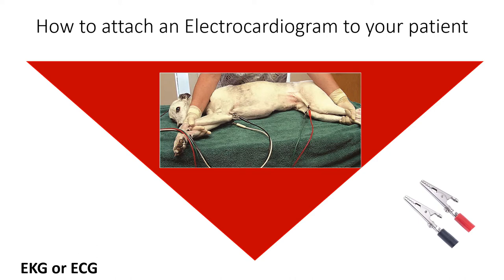When clipping or attaching the alligator clips to the limbs, place the leads just above or below the joints, i.e. the elbow and the knees. When joints are bent, they don't have a lot of circulation. Leads can be placed closer to the carpus and tarsus, but you may see more interference there.